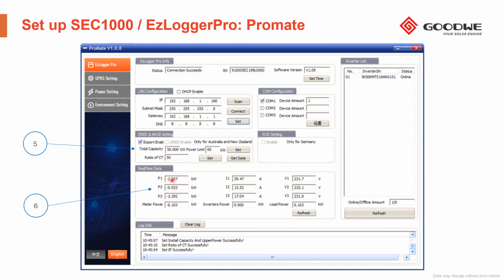So if we see here a positive value when the PV system is off, that means that the CT is not reading properly. Probably we need to change the direction of the reading of that CT. So it's a very good point to check, right? These kinds of things. And eventually the last thing is the IP. We can select the dynamic IP by clicking here, or we can set up a static IP.